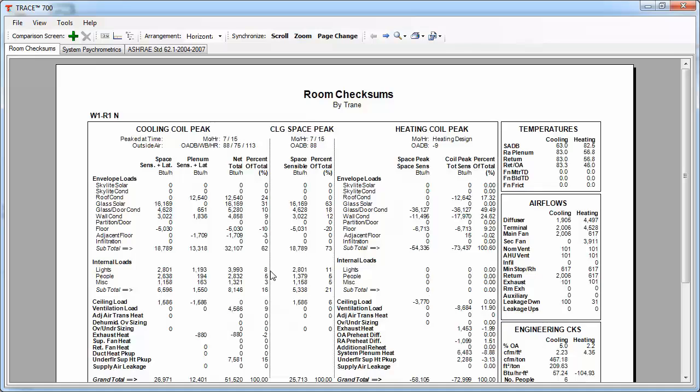Another thing we can take a look at is the cooling coil peak section, which is going to display the entire load that the coil is going to see, which is from the occupied layer and the unoccupied layer. This is important because then you can verify that your input is going to match what is in the output here. So, for the lighting, I said we're roughly 4000 BTUH. You can see that the net total that the coil is going to see is 4000 BTUH. Another interesting thing to look at are the floors and adjacent floor loads, and this is where you can kind of decide and see whether or not this load is reasonable based on what you've inputted in for your floor construction.